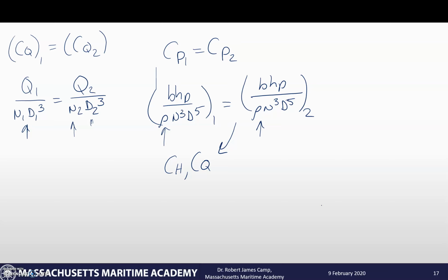And so a lot of times what will happen is, okay, we have one pump. We want to make another style. We want to take that pump and make a couple of different versions of it. How is it going to act? Do we have to build that pump and test it before we can do it? No, you can actually take a look at this and go, okay, I know this pump is here, and this other one's geometrically similar, so I can calculate out what all of the data for that geometrically similar pump is going to be.